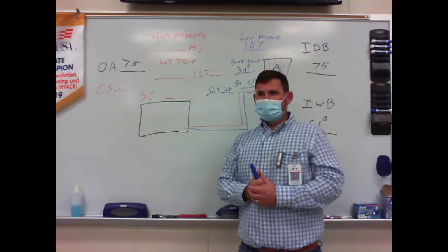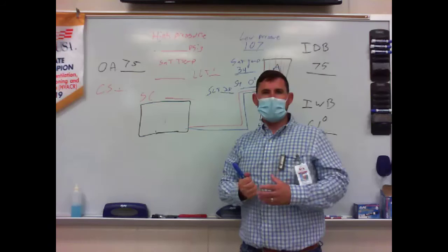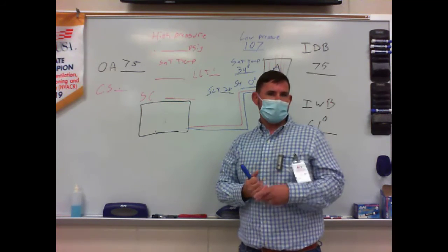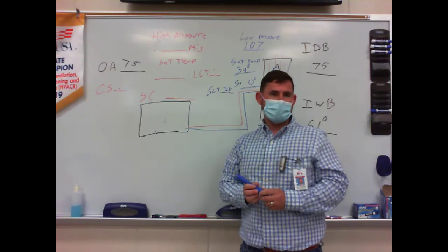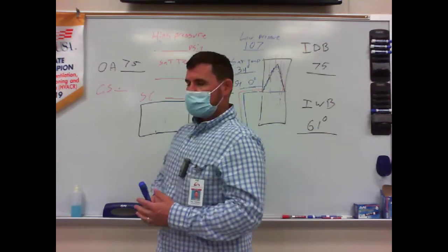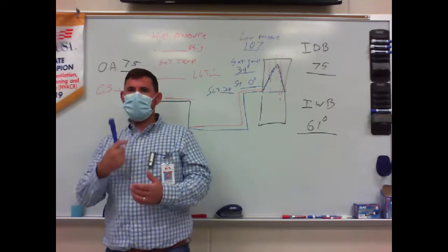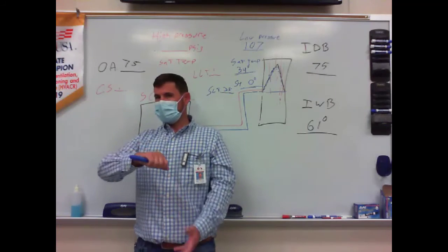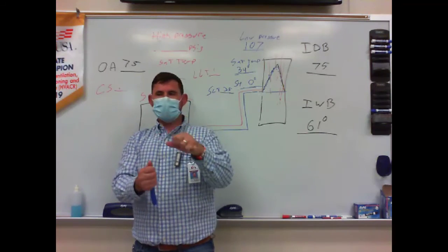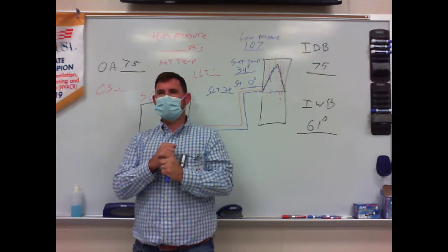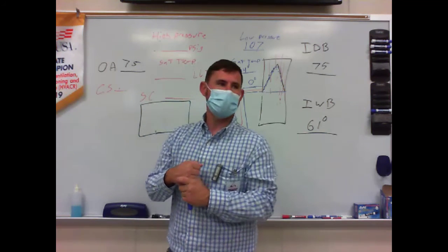Make sense? So those of you, we've analyzed your system, we know what to do now, right? We're going to add some refrigerant to it, and Josiah's, we're going to check it out just to see if there's something we need to do to it. To add refrigerant, 410A has to be added as a liquid, right? We got to flip that tank upside down. Do we weigh it into the high side or the low side? We have to weigh it into the low side. Why?